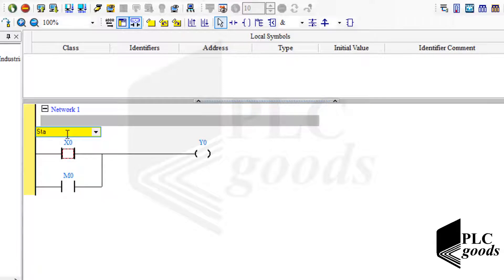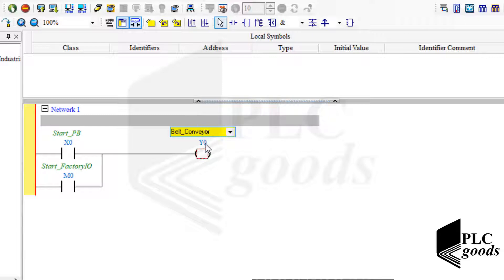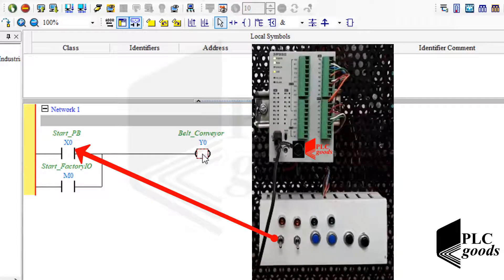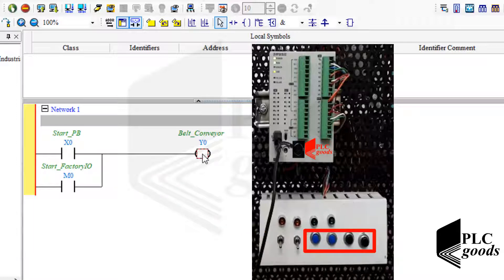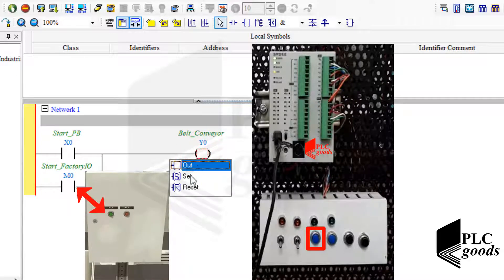If you remember, I used that to start the belt conveyor. Now let me add suitable symbols. Note that usually a simple coil is used when a switch is connected to the PLC, because a switch latches its last state. But in industries, push buttons are usually used to start or stop a process. So to use this real push button and also this virtual push button, let's use a set coil.